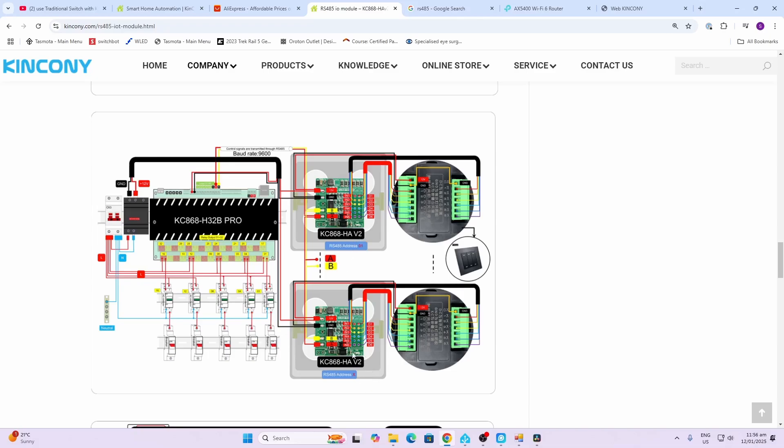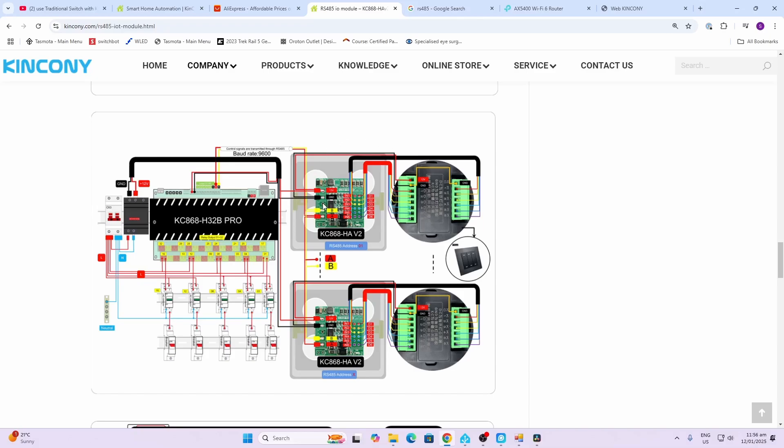Remember there is a jumper on the board. You would install the jumper on the last device in the line. On the other side we connect the gang switches. So gang one would go to K1, gang two would go to K2, gang three to K3, and then the other side of the switch would be just connected to the neutral line.